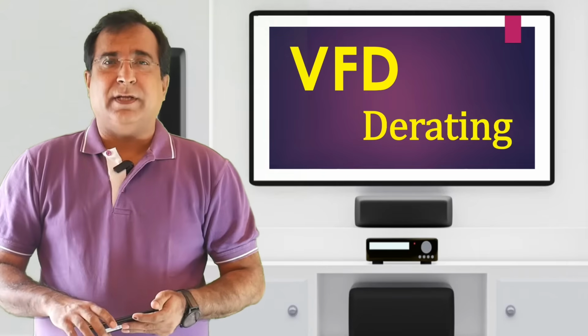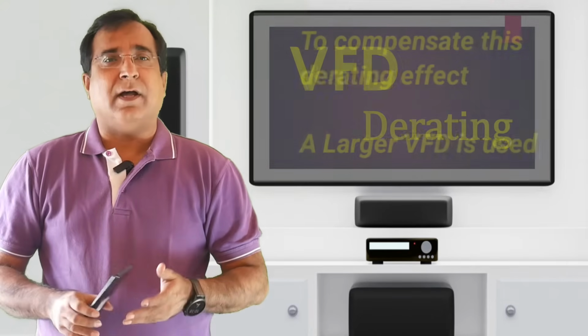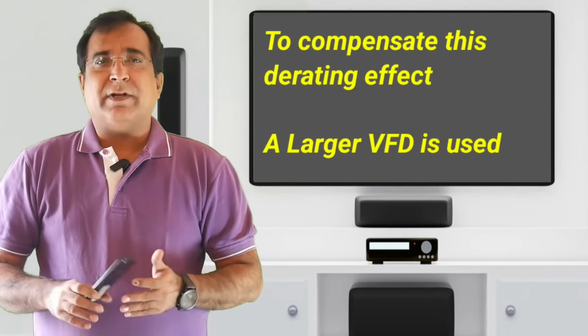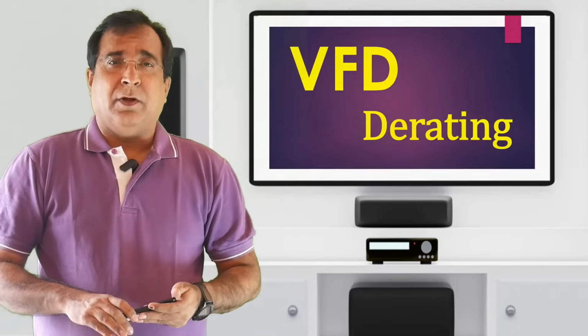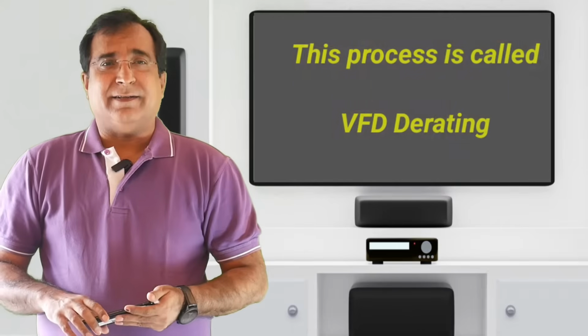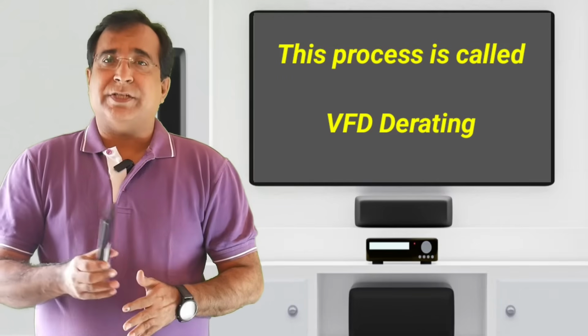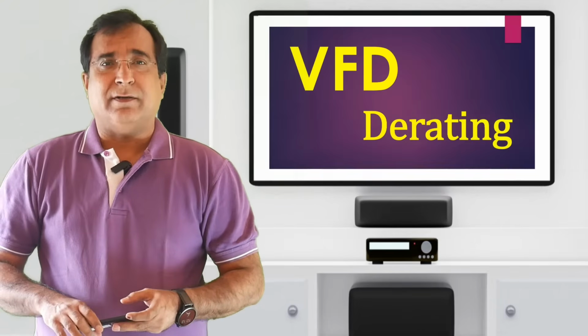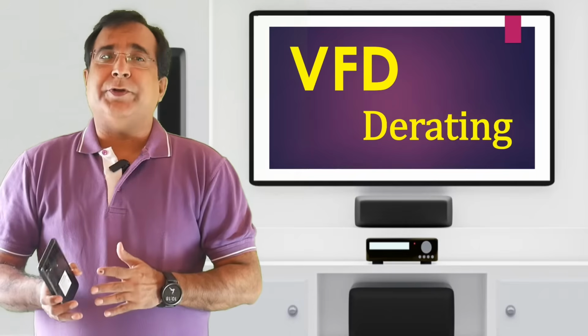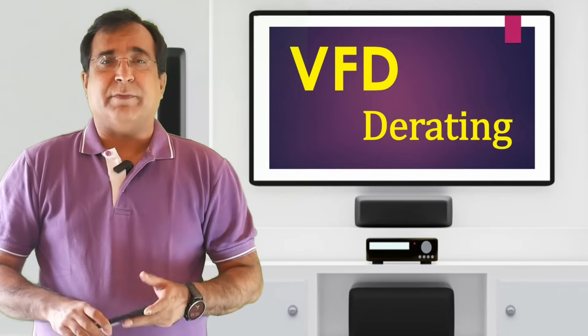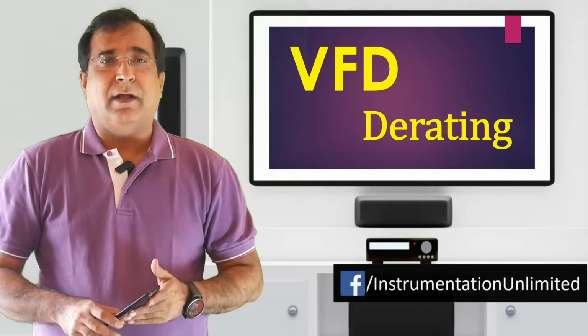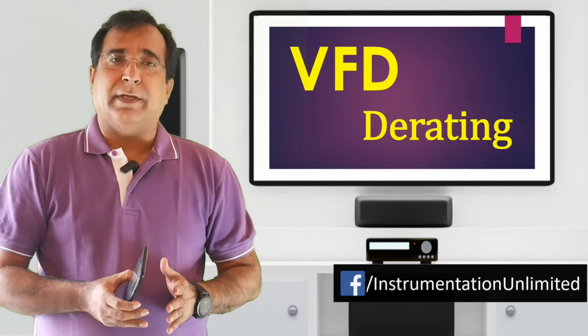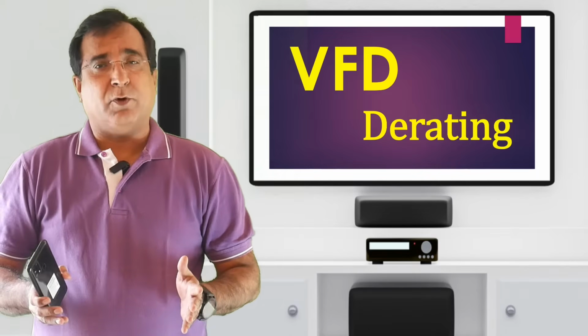For these reasons only, such applications require a VFD larger than the normal, even as per motor design VFD. Now this process is called VFD derating. That means you are intentionally using a larger VFD than the required, because altitude or higher surrounding temperature will reduce its current rating, and you want the VFD to operate normally and handle load safely without tripping the motor.